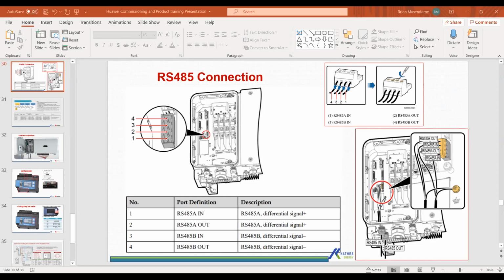Just make sure your RS-485 line doesn't pass through high power cables, because of noise. And if you have such long distances, preferably use shielded cable to keep out noise.